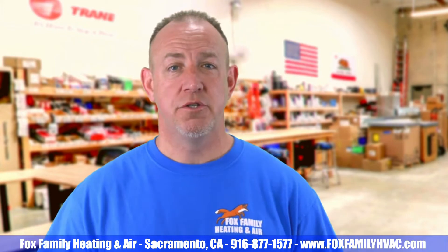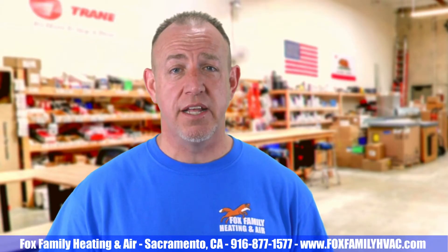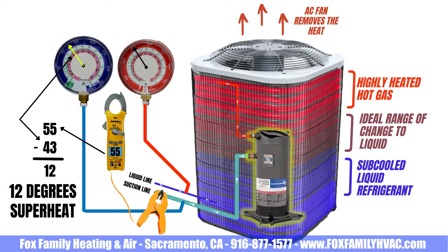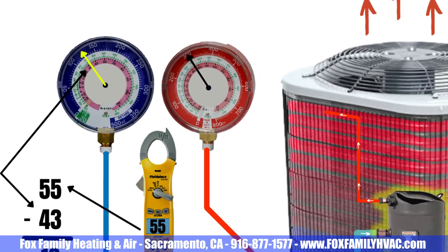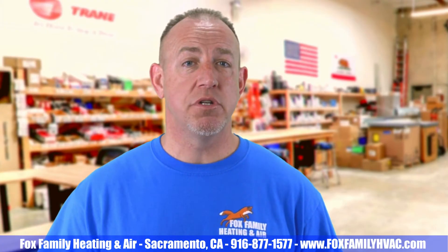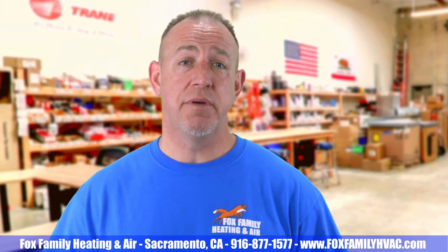So let's get into faulty TXVs. You can tell what your TXV is doing by checking your superheat and subcooling — it lets you envision the state of the refrigerant and where that crucial point is in the system where the liquid turns to gas. Superheat is the difference between the suction pressure converted to temperature and the actual suction line temperature. For example, 125 PSI on the suction side — looking at that inner pink R410A ring on these Yellow Jacket gauges translates that pressure to about 43 degrees. That means the temperature of the evap coil is 43 degrees. The closer to 32 degrees that evap coil temperature gets, the closer it is to frosting up and eventually turning into an ice block.